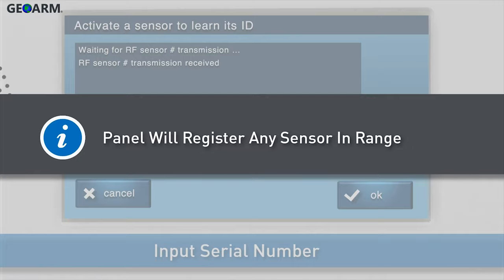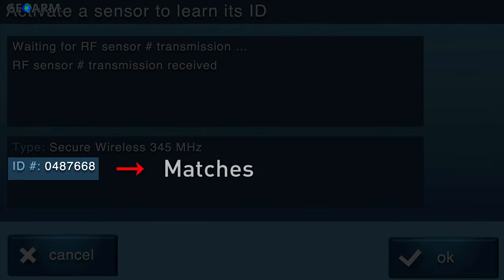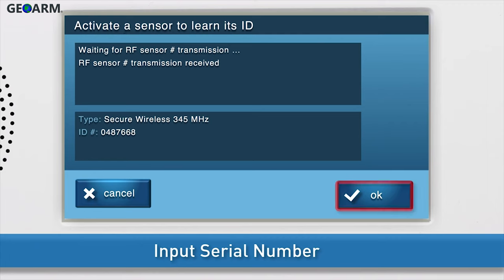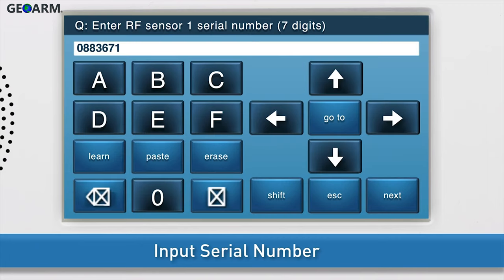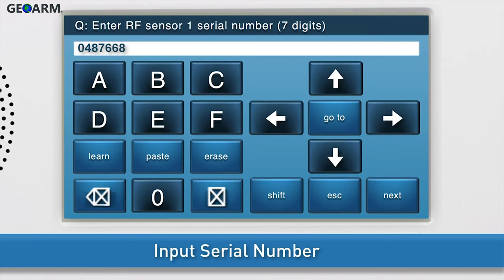You will see the confirmation message and ID number on screen. Note, the panel will register any sensor within range, so you will need to make sure the ID number shown on screen matches the serial number of the detector you are adding. If the ID numbers do not match, press LEARN once more and trigger the detector again. Press OK as soon as the correct ID number displays on screen. You will see the serial number or TXID number in the answer box. Press the down arrow to go to the next sub-question.